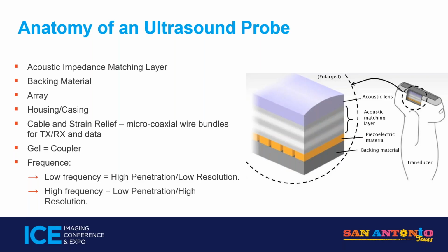And you can look at the acoustic impedance matching layer, and that's the actual acoustic lens. It has to be there. People will always, all the time, look at a probe and it will have chunks of the lens material missing. Does it still image? Absolutely. So the sonographer continues to use it. But what they don't really understand is that lens is actually acoustically matched to allow the ultrasound wave, the sound wave, to go into the human body in the correct way. So when you remove that layer, that lens, through damage or wear, it actually affects your image quality.